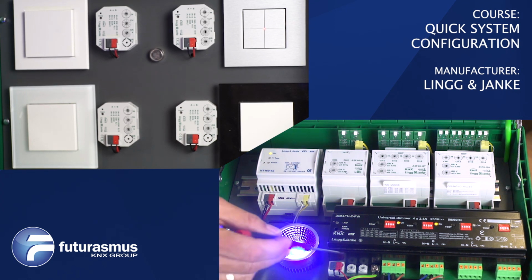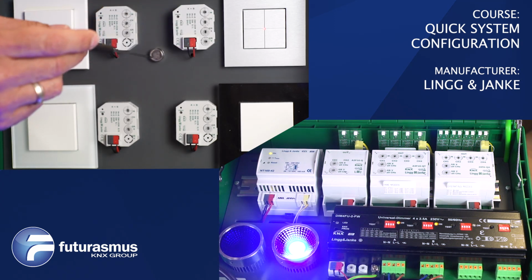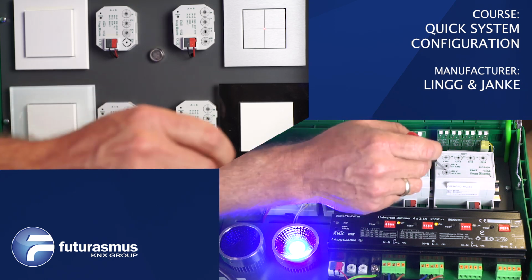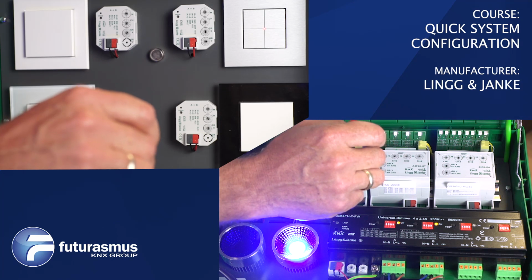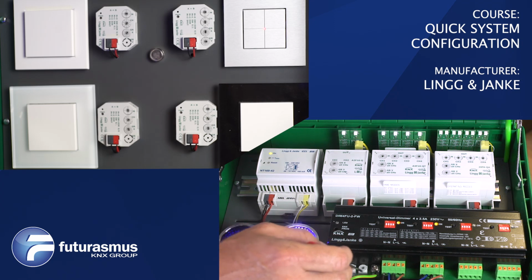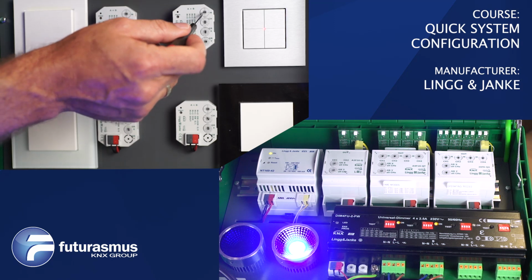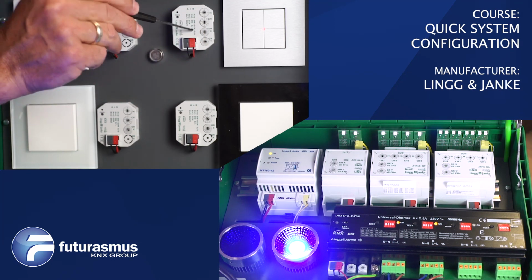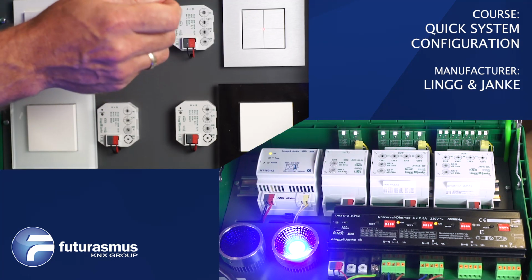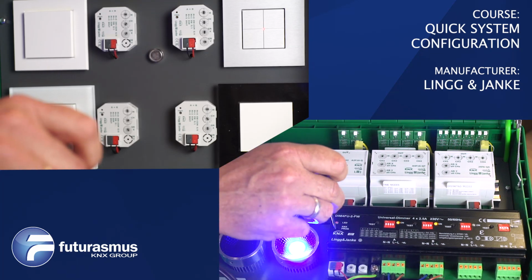Now let's say we want to switch, for instance, the dimmer off with a central on-off function here. So for that, we need to set up the Y. Let's put all the Ys to 4. So we will put the Y, for instance, here for the lightings, 4. And the Y in this one, we set it also to 4. And we use the central off function, which switches off always. So we use this one to 0. And now we can program this one again. And we can program the dimmer, which was the one which has been changed.